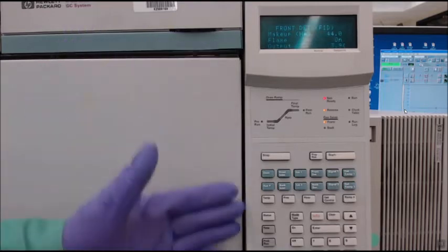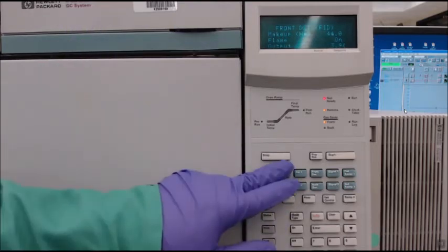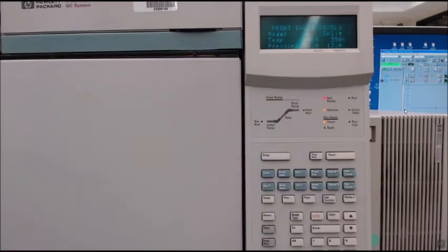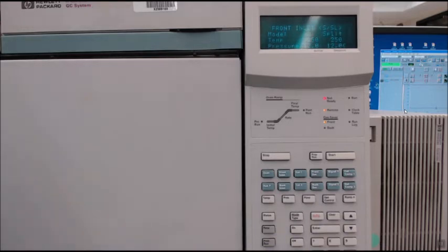So, we've gone over what we're looking for. However, on the inlet, there is a possible troubleshooting issue. You see this pressure setting. If that is reading low, it is possible that you may have a leak. If this happens, the machine will not run. Please consult your TA.